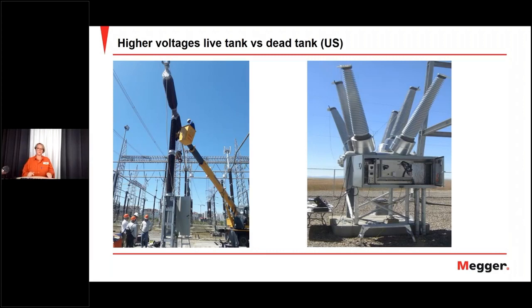We come up to the bigger breakers. Here are outdoor breakers, a live tank to the left and a dead tank to the right. Dead tank, American type of circuit breakers, has a lower point of weight, so it's more stable than the pole types to the left.